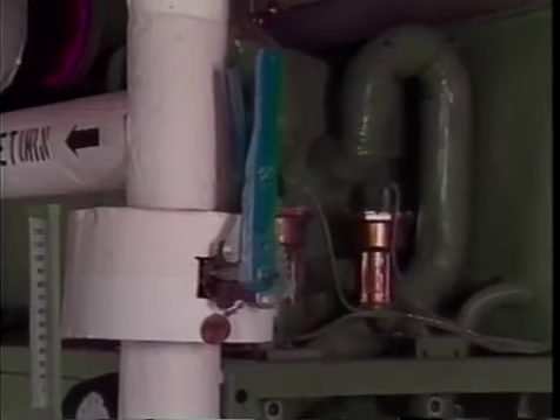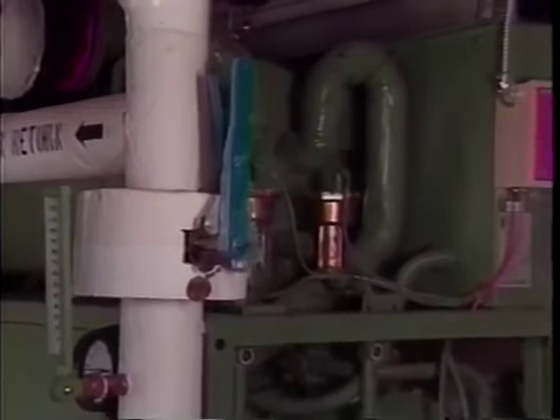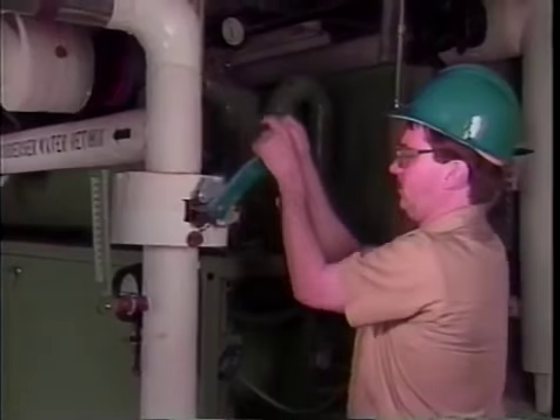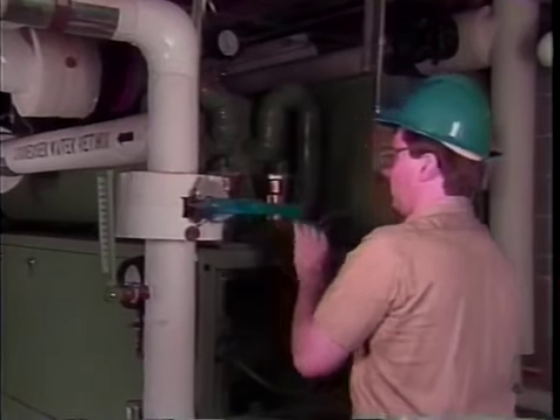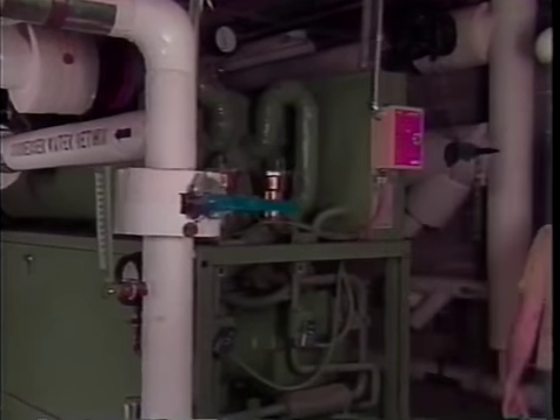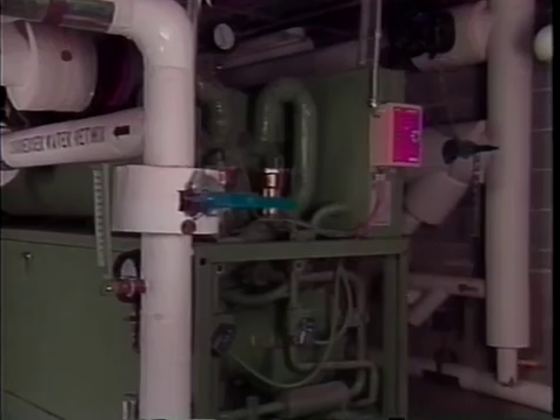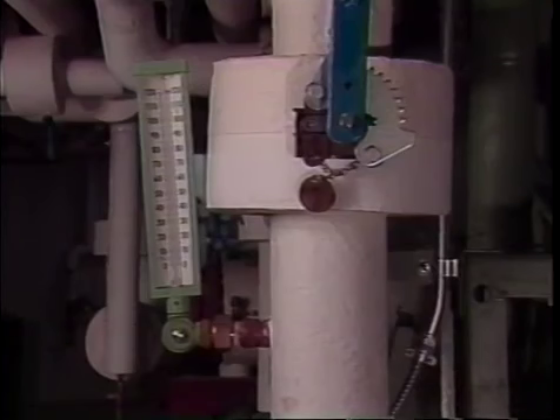When shutting down and isolating a heat exchanger, close only one water valve, not both, to allow for expansion of the fluid. If it's necessary to close both valves, then leave a vent open. Thermometer wells for taking temperature readings across the heat exchanger should extend into the nozzle or piping at least 3/4 of the diameter of the pipe.